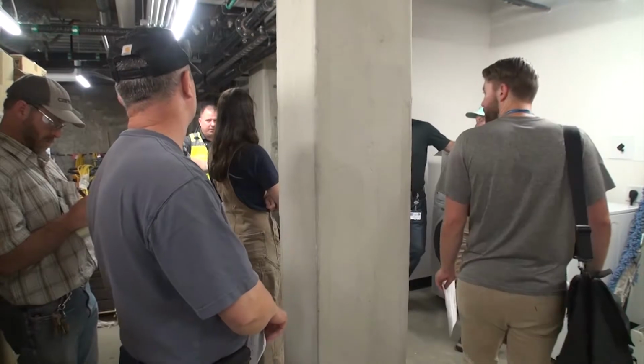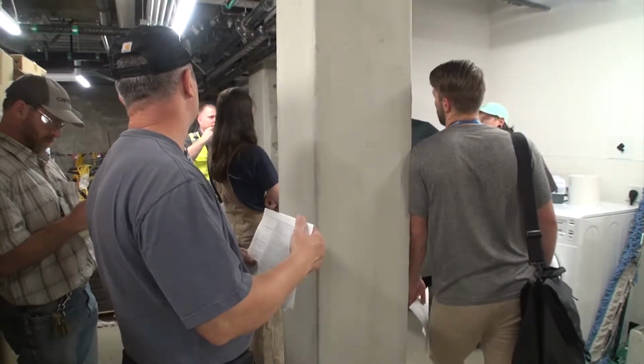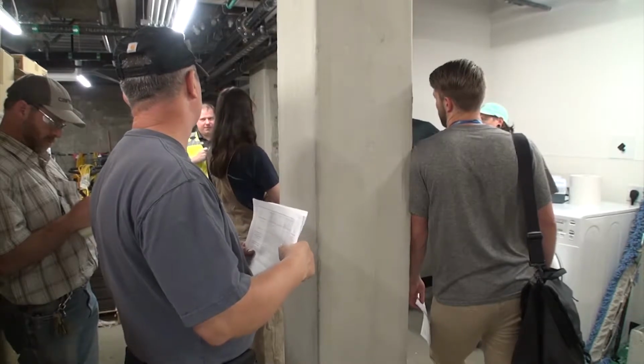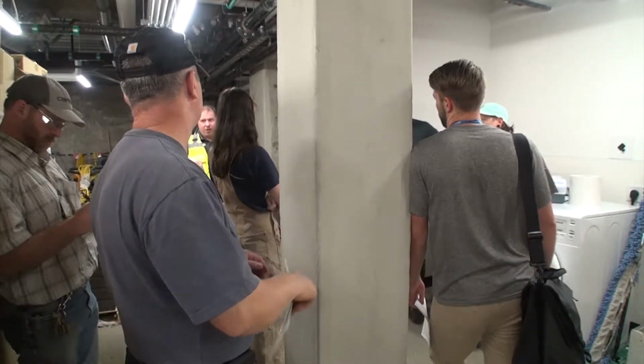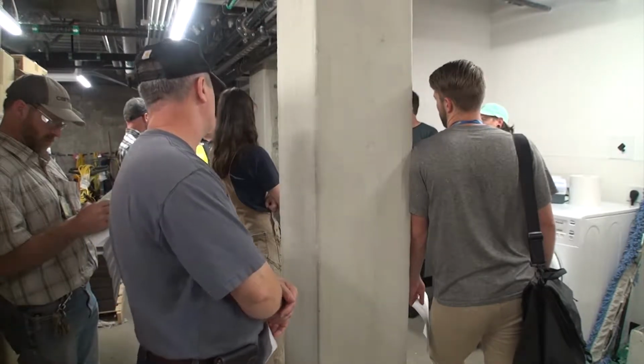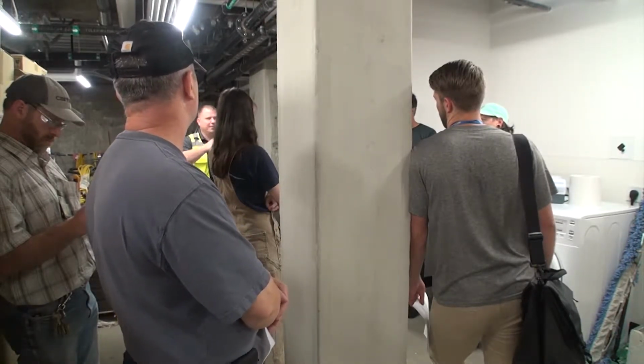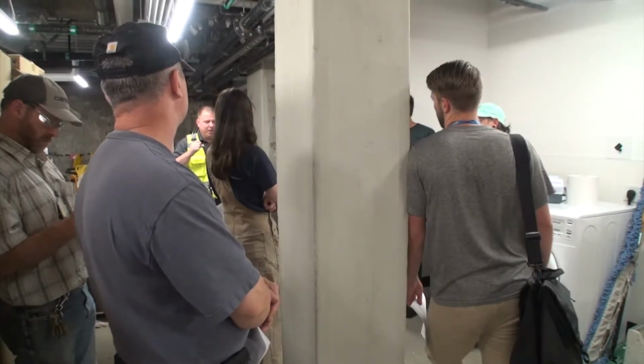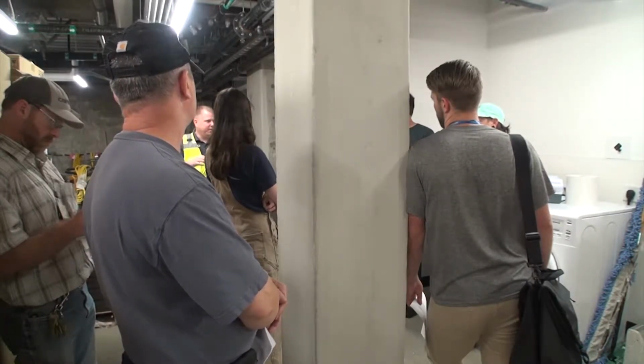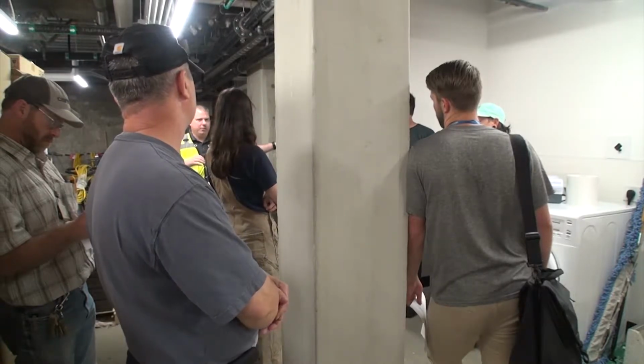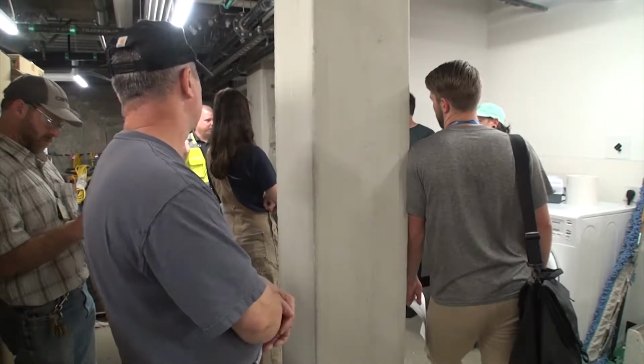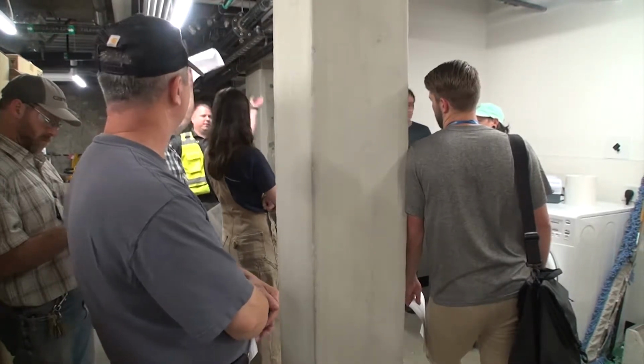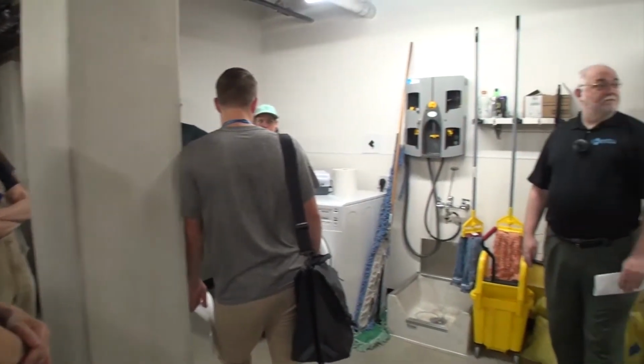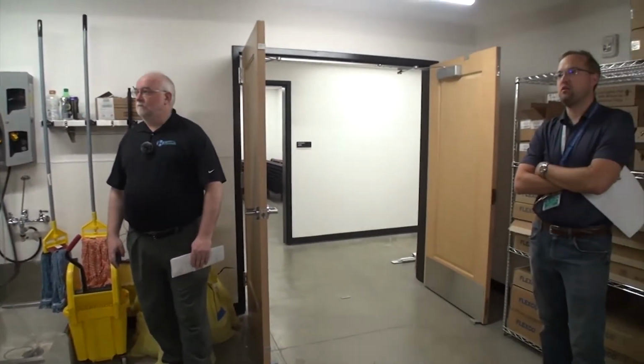Microphonics will keep lights on, they won't automatically turn lights on. So you leave and you turn the light off and this is running. Yes, you're probably good. There is a grace period, so if the lights shut off, you have like 10 seconds, I believe. I always forget, but 10, yeah, he's nodding at me. So 10 seconds where you've got a teacher that's quiet at the desk and his lights shut off. He doesn't have to get up and manually turn the lights on. He could just go, hey, and the lights will turn back on. The clarification there is that if you turn the switch off, it's not going to come on because of motion or sound. It's when it times out, it'll come back on, right?